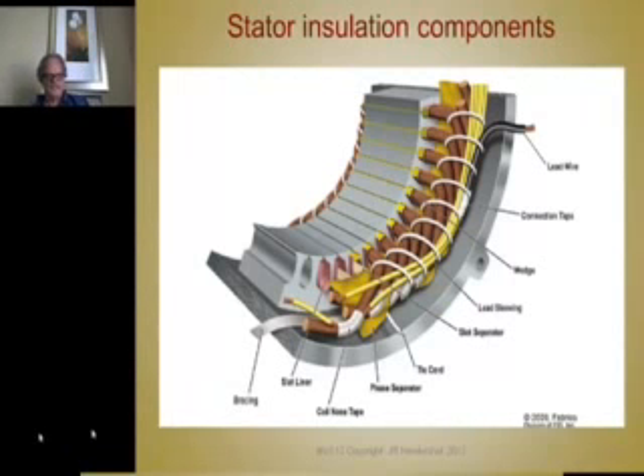There are a few things that are worth pointing out. Here's the slot liner right here. These don't have to have cuffs on them, but they're longer than the core, so they still keep the coils away from the face of the core. Then you have what are called top sticks or slot wedges that go over the top. That's to keep the conductors from coming out of the slots.